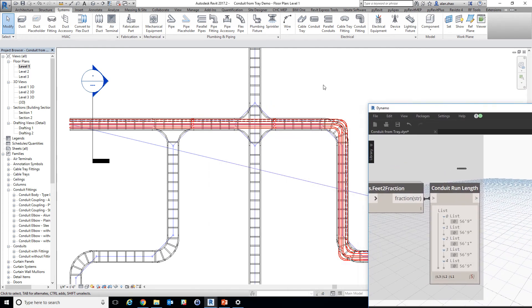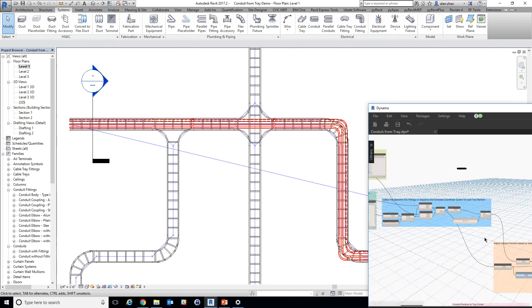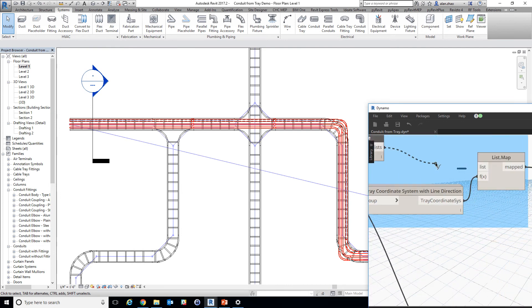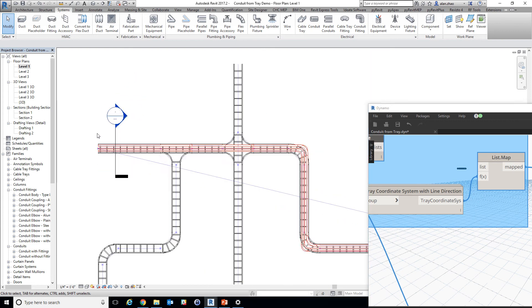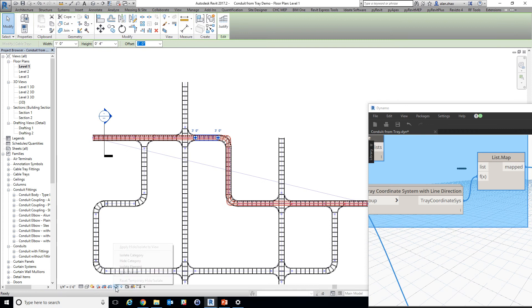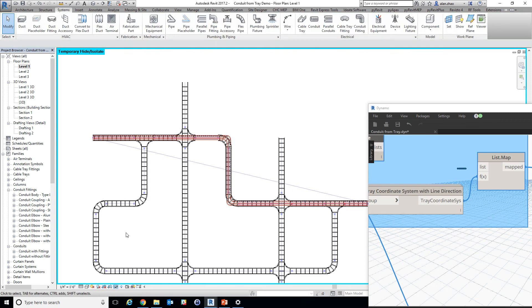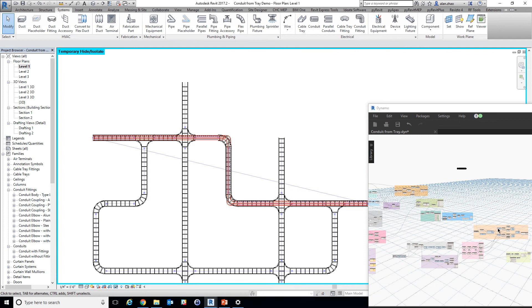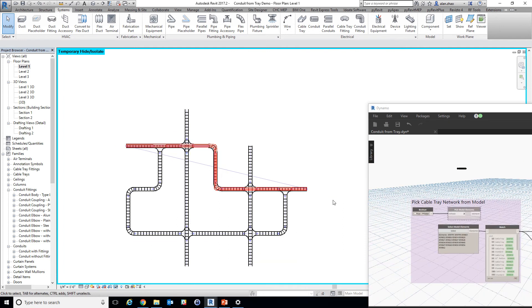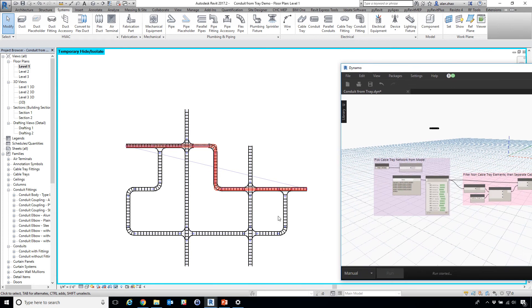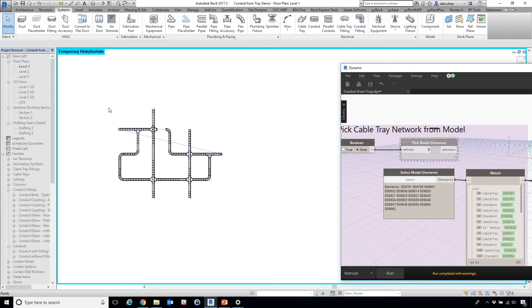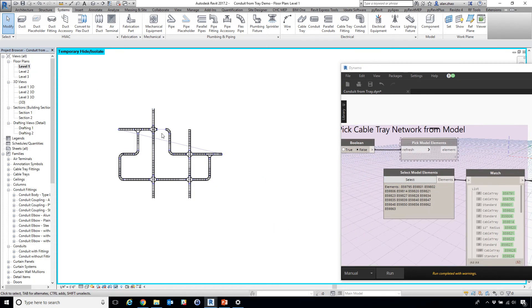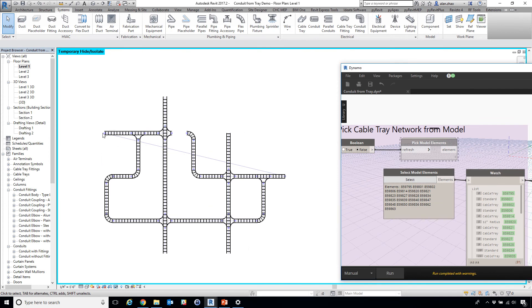So if you ask me what if we want to take specific route, well of course we can do that. What we're going to do is to hide a certain element when we select the tray network so that it will force the code to find the next shortest length. For example, if we're going to hit run again, so it will remove the previous conduit. And we're going to select this new network where we're missing that part. Hit run, see that's not highlighted. Again from this start to that end, it's going to force to take a different route this time.